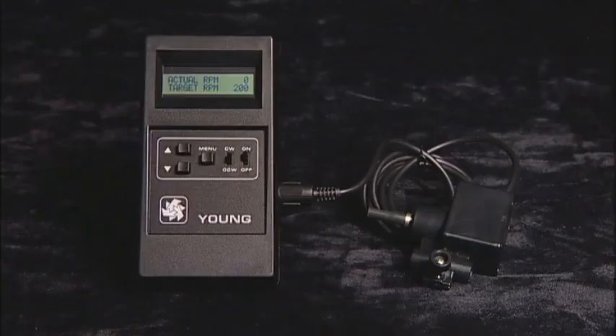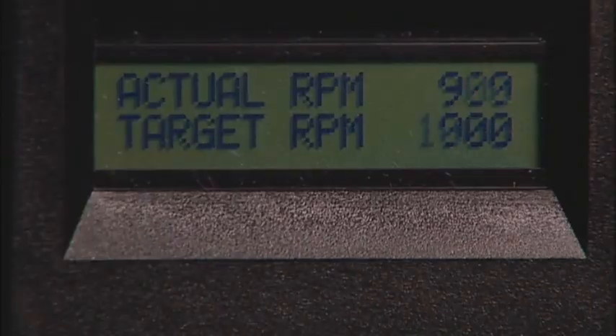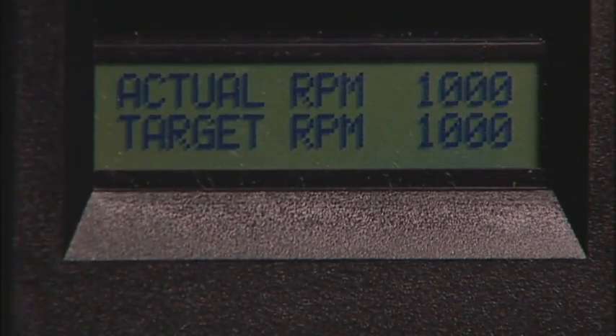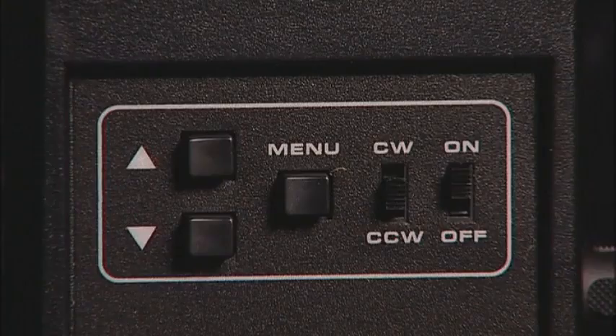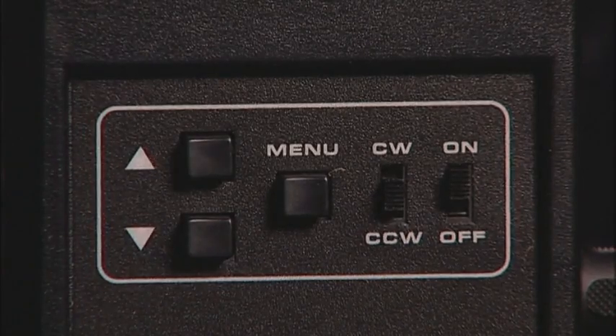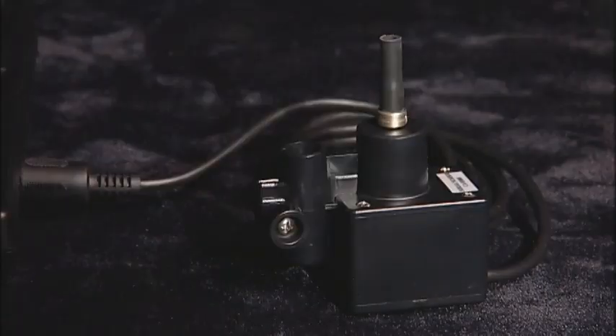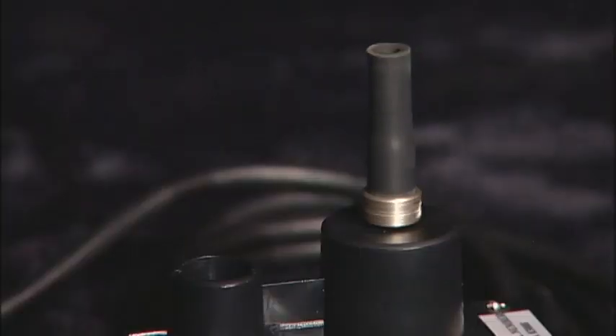The device that we shall use to reference the upper range of the wind speed sensor is the R.M. Young model number 18802 battery-operated motor and controller unit. This unit can generate RPMs from 0 to 15,000 RPM. Notice the controller unit has a toggle switch for on-off, direction, clockwise or counterclockwise, and speed. The motor is attached to it via a cable. Once the unit is turned on, the controller controls the speed that is generated. Note the rubber grommet at this time will be used to attach the shaft of the motor to the shaft of the anemometer. The control unit allows the user to switch speeds, thus changing the response of the anemometer.